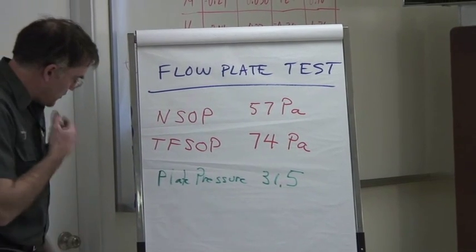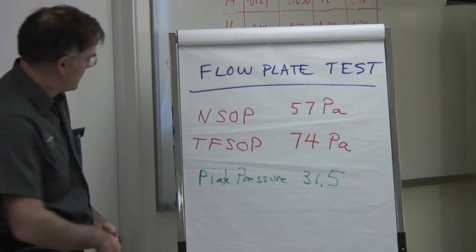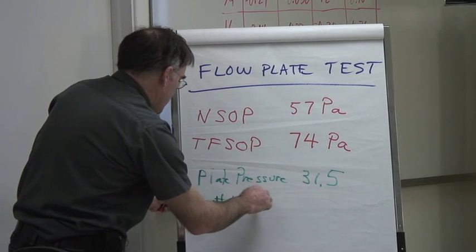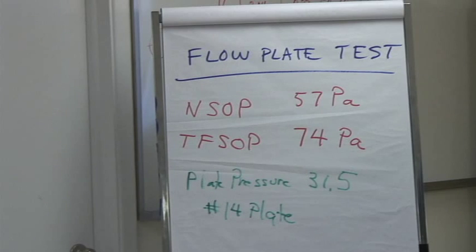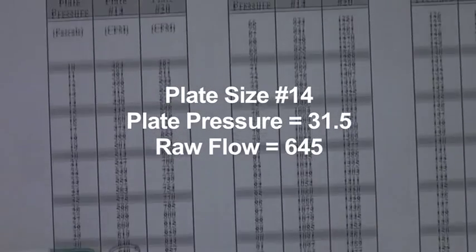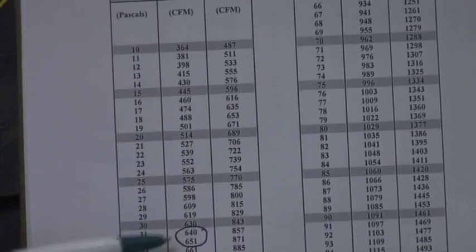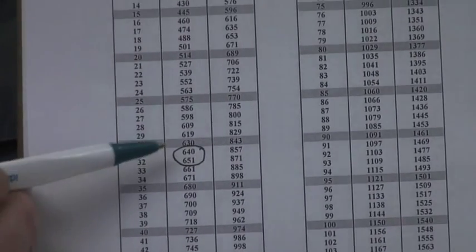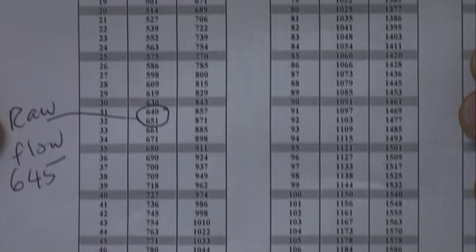We're ready to actually get to a flow and a correction. The plate we put in was the number 14 plate. We have our measurements. All that's left is to look up what we call the raw flow, which is what came off from our plate pressure and our plate size, which was the number 14. We were kind of in between 31 and 32 Pascals of plate pressure, so a flow between about 640 and 650 CFM. Let's call it 645.